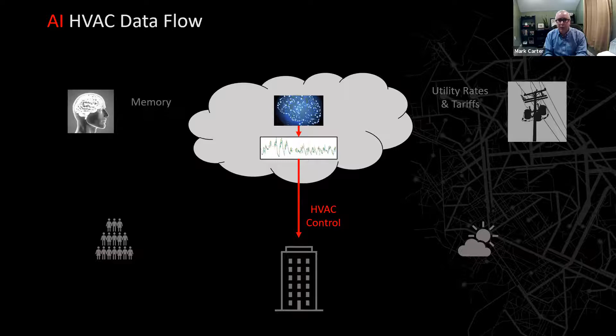So as I mentioned, it does come up with modeling, and that's really the key to this. If you can't model it, then taking control action on bad data is not very advisable. So you really have to be 98, 99% accurate of a zone temperature 2 hours plus into the future. And that's really the baseline of what the artificial intelligence algorithm is doing before it actually makes a control move.